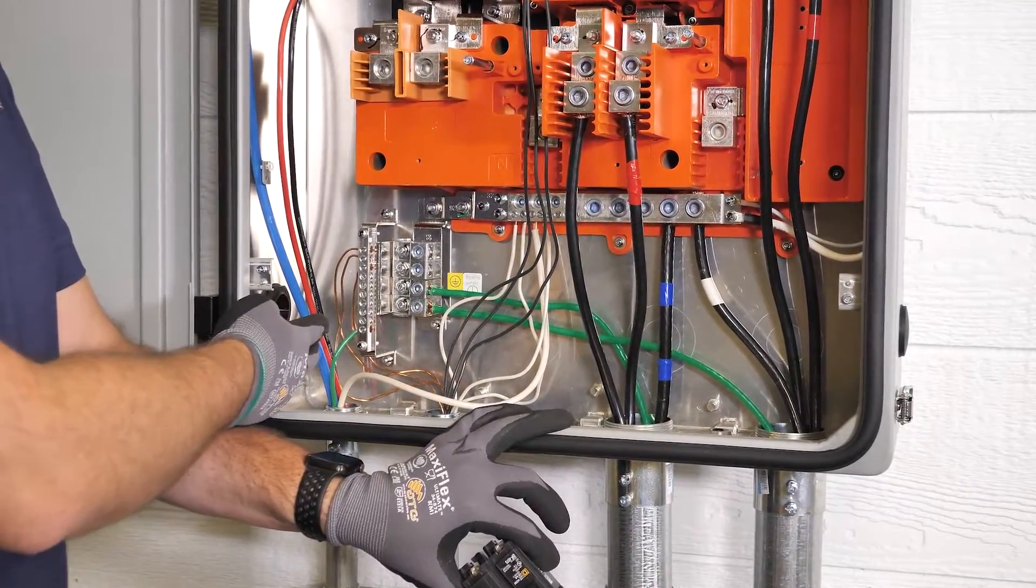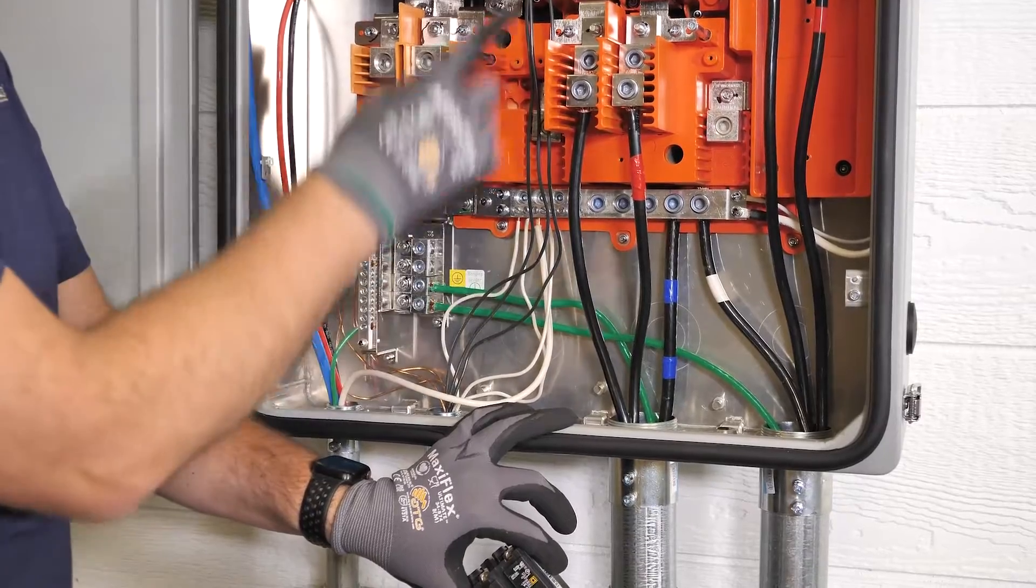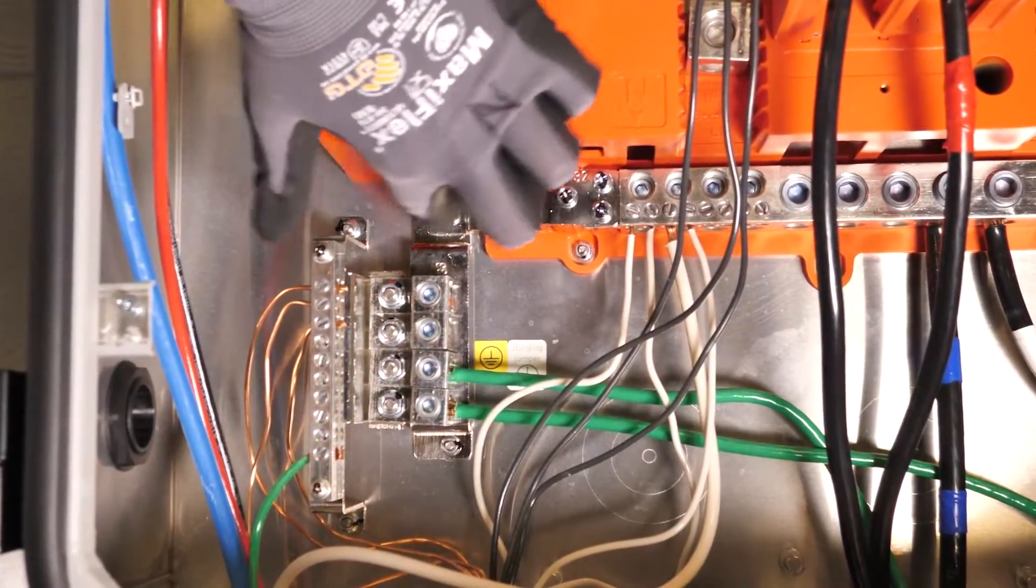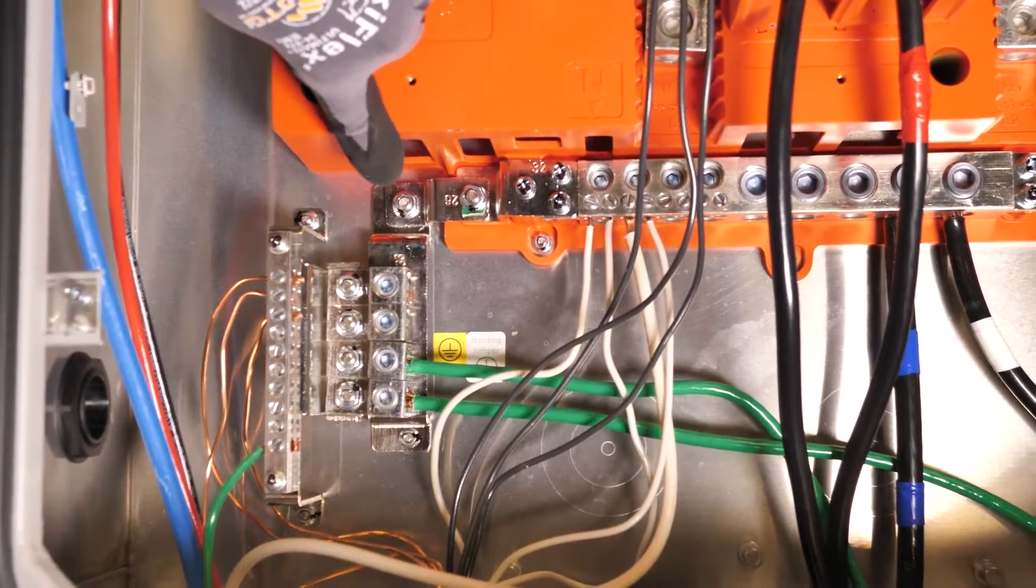Ensure that all equipment is properly grounded. If the smart box is not a service entrance, make sure that you remove the neutral ground bonding bar.